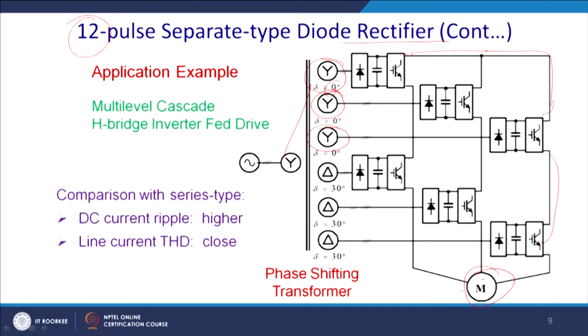So, in that way this 3 phase has been generated by cascading the 12 pulse, and ultimately it will cancel out the effective harmonic and give you a good quality drive. This is generally the way of feeding a multi-level; these are all cascade multi-level inverter topologies.